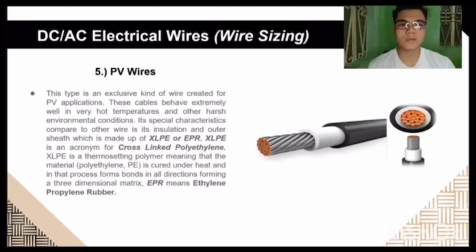PV wires. This type is an exclusive kind of wire created for PV applications. These cables behave extremely well in very hot temperatures and other harsh environmental conditions. Its special characteristic compared to other wire is its insulation and outer sheath, which is made up of XLPE or EPR. XLPE is an acronym for cross-linked polyethylene. XLPE is a thermosetting polymer, meaning that the material polyethylene, or PE, is cured under heat and in that process forms bonds in all directions, forming a three-dimensional matrix. EPR means ethylene propylene rubber. It is a single conductor wire used to connect the panels of a photovoltaic electric energy system.